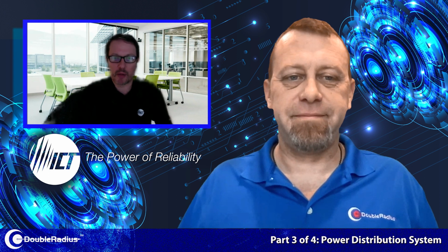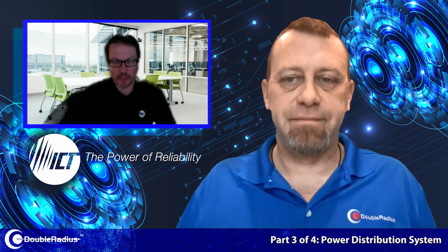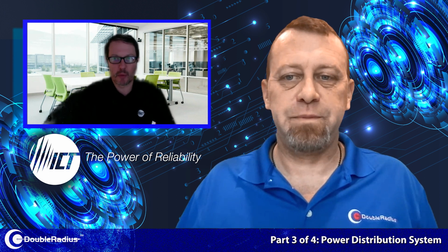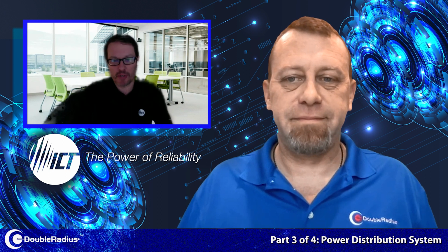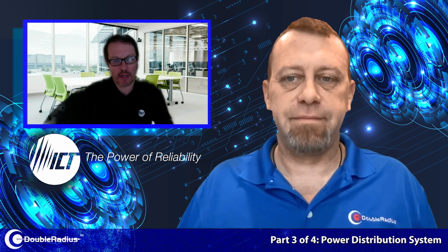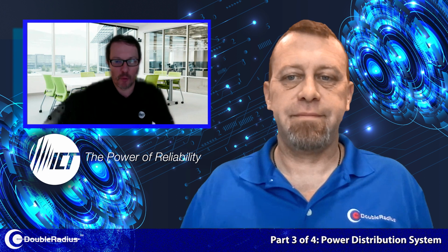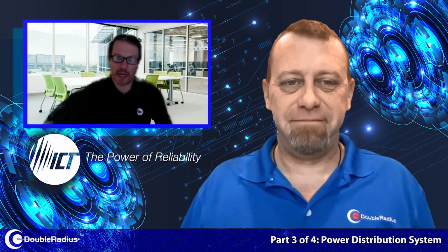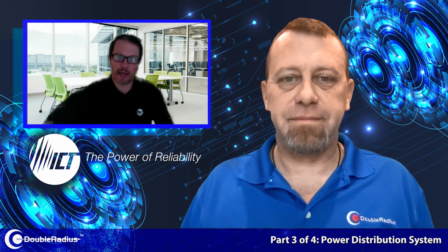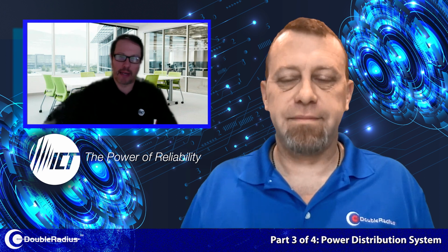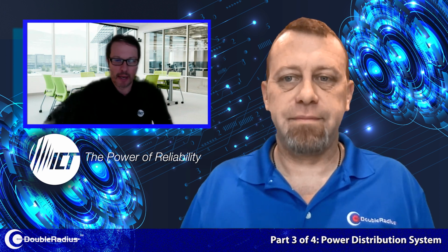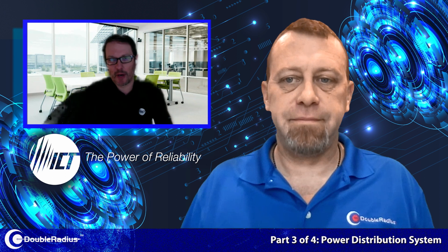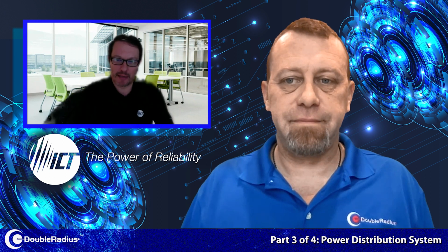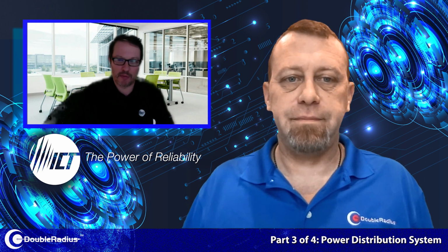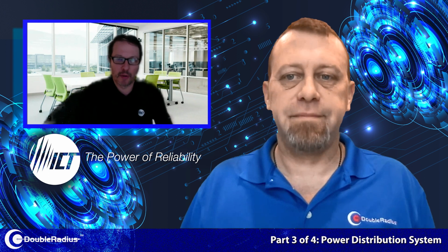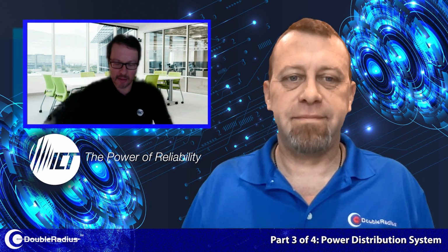So we have what we call single bus DC distribution panels, and those ones are typically utilized where there is just one DC voltage that is needed at a communication site. It might probably be 48 volts DC, in which case you just have a single bus and the DC voltage is fed in and distributed to your loads. We have various different ones that can provide fused outputs, a variety of fuses, GMT fuses, ATO fuses, etc. So depending on the customer's needs.